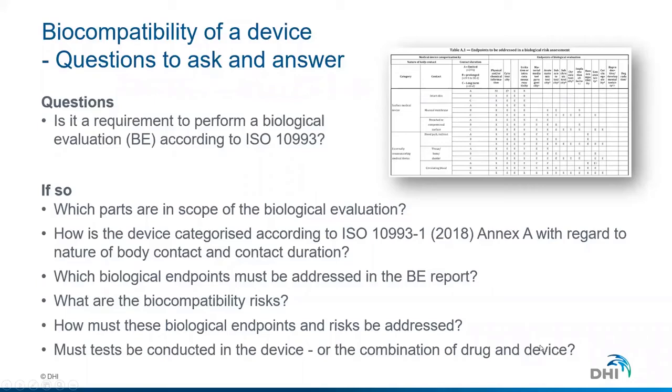So that could be that, like in the implantable hormonal rod, then you need to consider the rod material in the conformation of the rod itself, as well as the rod as it appears with the hormone inside it, because the reactions to the materials and to the rod may differ depending on whether the hormone is there or not. So it's quite important that you carefully consider how you want to test your device when you plan the testing.